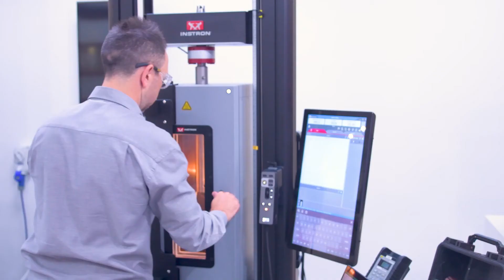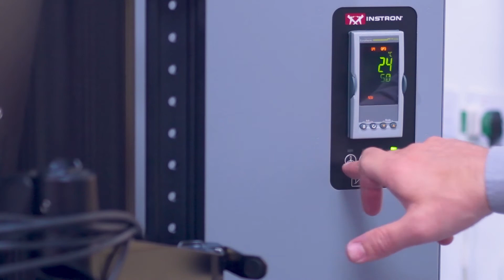Instron can perform two types of temperature calibration services in the field. The first one is referred to as in situ and is performed by placing calibrated thermocouples in the chamber being verified and comparing their reading to the system's reading.